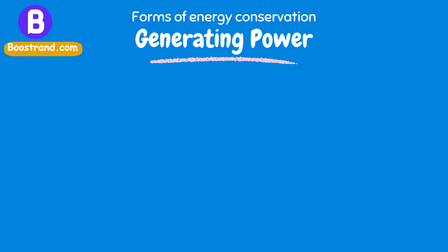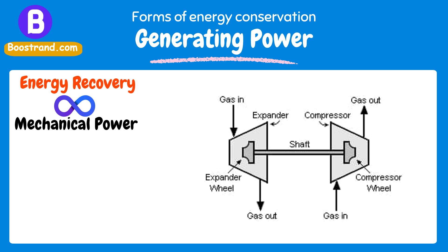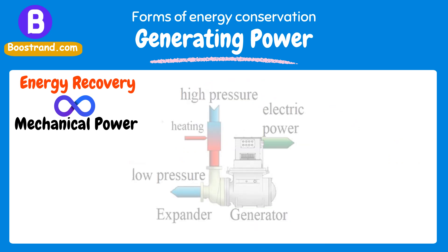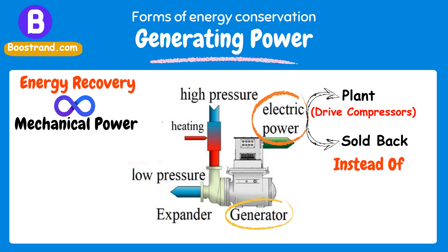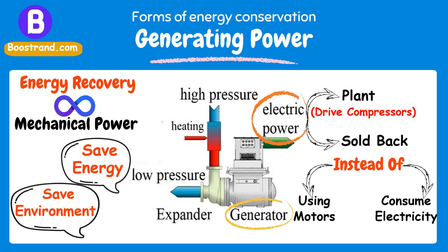The third way is generating power. Energy recovery is not just related to heat transfer, but is also commonly used in mechanical power. A famous example is the use of turbo expanders to generate mechanical power that can drive gas compressors. Turbo expanders are mechanical devices that remove energy from a high-pressure process gas stream, resulting in a simultaneous drop in both pressure and temperature, and the removed energy is converted into mechanical energy. Generator-loaded turbo expanders convert the recovered energy into electricity, which can be used within the plant or sold back to the local electrical grid. Otherwise, if we have compressors in our process, they can drive the compressors instead of using electric motors consuming megawatts of electricity. This shall result in significant energy savings and much less gas to be burnt for power generation, which means less carbon emissions.